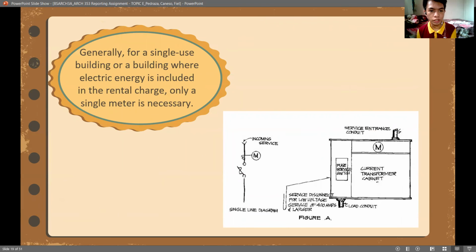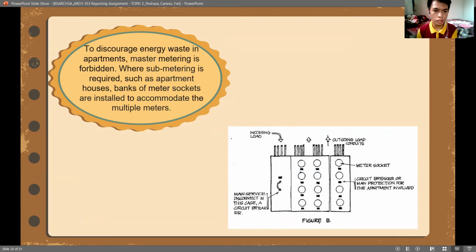Generally, for a single-use building or a building where electricity is included in the rental charge, only a single meter is necessary. So for houses or buildings, single-use buildings, we only use a single meter. The next one, to discourage energy waste in apartments, master metering is forbidden. Where sub-metering is required, such as apartment houses, banks of meter sockets are installed to accommodate the multiple meters. So apartments use sub-metering, and they can't use master metering to discourage energy waste in apartments.